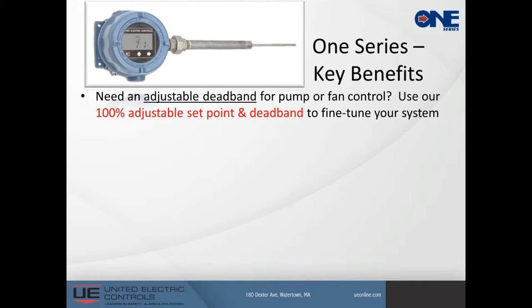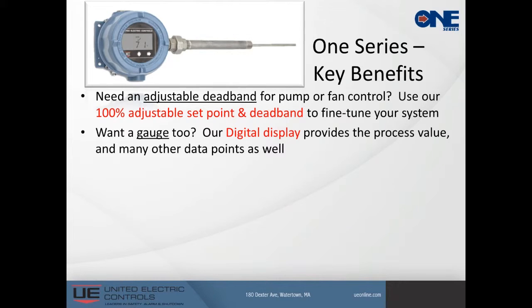So some of the key benefits here is that this switch has a fully adjustable deadband, as opposed to a mechanical switch, which you live with what you get. So from the face, you can program your set point, and you can also program in your deadband from 0 to full scale. You make that adjustment. That's up to you. It has a local display on it, and this local display is what we use to program the device, read the process variable on this device, and it also gives us some data back as far as the health of the device and also the capability to interrogate where the device is seeing minimum and maximum extremes. So it's all done from the front end of the display that you're looking at right now.